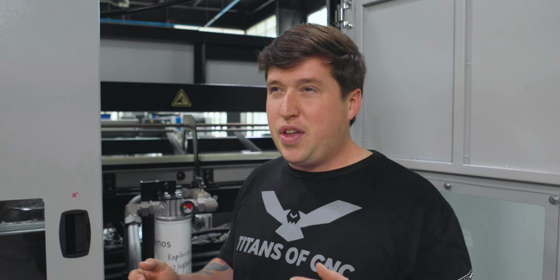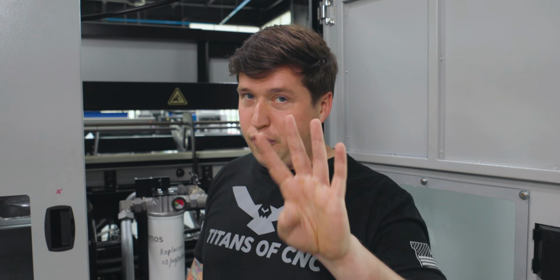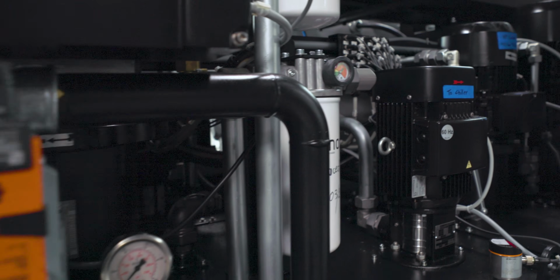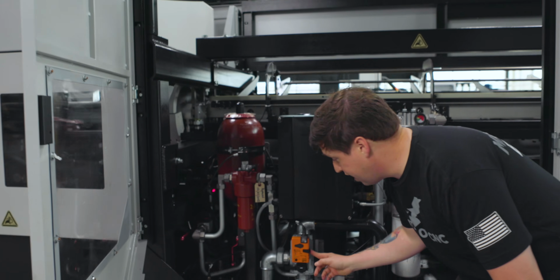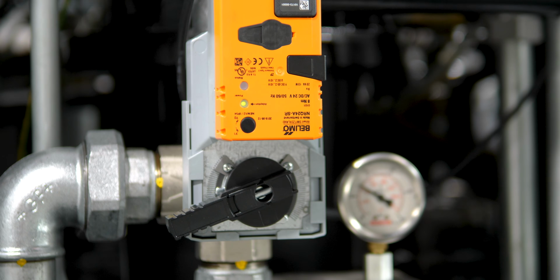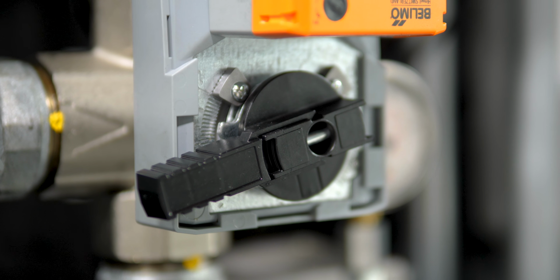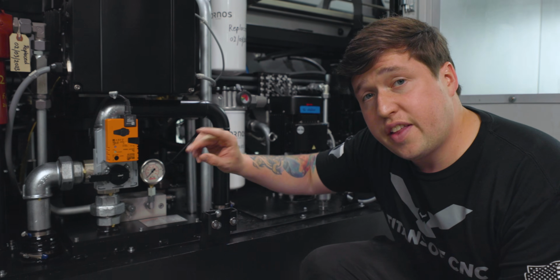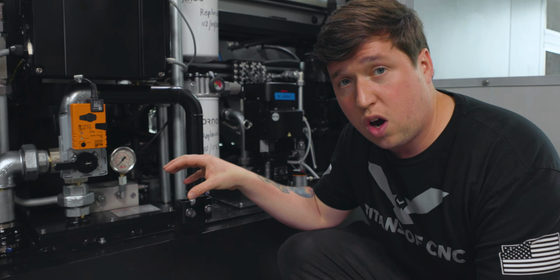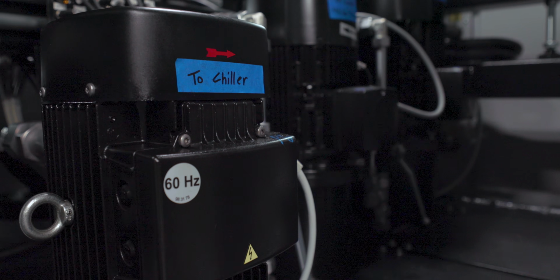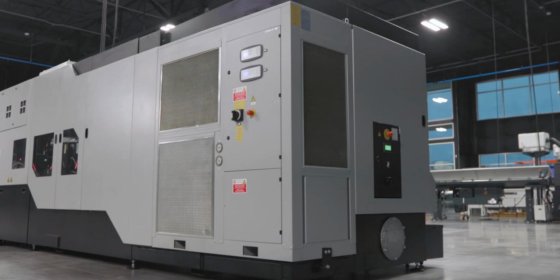All right, so you have your cold tank right here, and the rest of the oil in the machine is inside what's called the hot tank. This is kept at 30 degrees Celsius. Don't think hot and cold really means too big of a difference here. It's only 4 degrees Celsius. So the cold tank is monitored right here by this thermometer. While the machine's running, you'll actually notice this handle move up and down, keeping track of the temperature. Once this detects that the coolant in the cold tank is too warm, it'll activate this pump right here, which sends the oil to the 26-degree chiller.